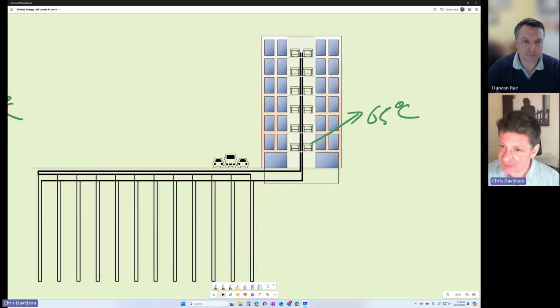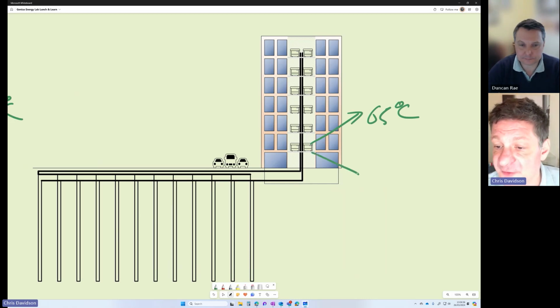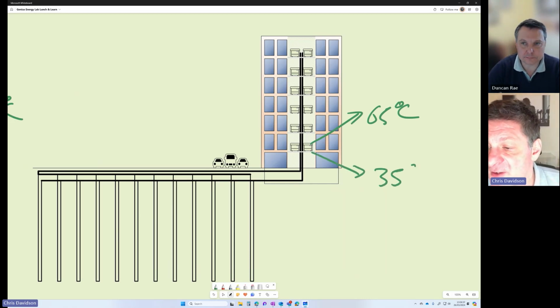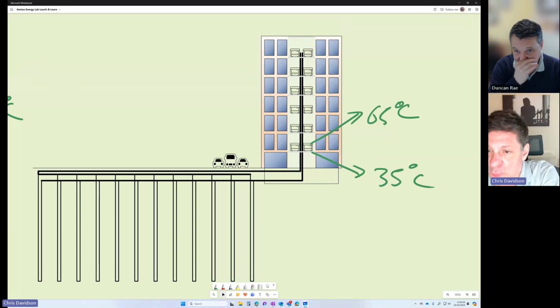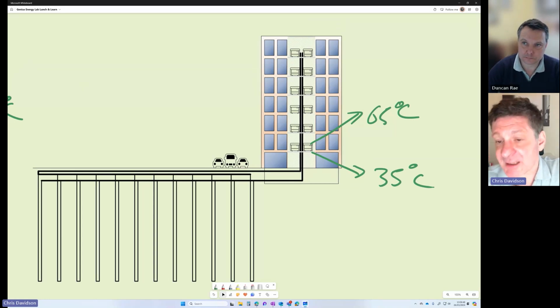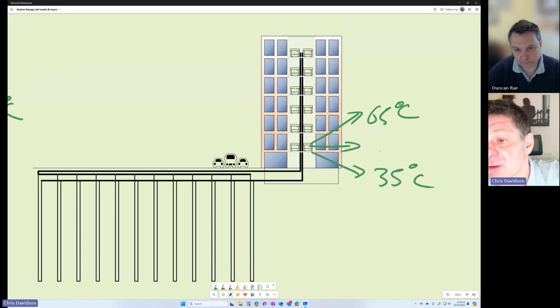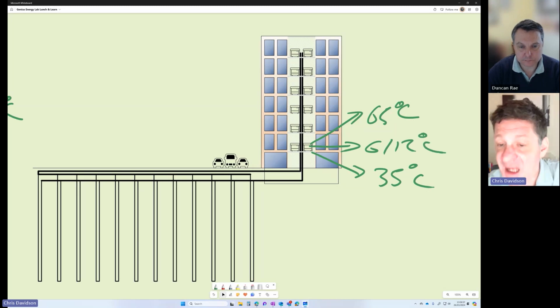And then they can turn off at that higher temperature and go to a lower temperature to deliver the space heating at 35 degrees. So we're now not compromising that space heating efficiency in order to deliver that domestic hot water. We could also be cleverer. Again, we could reverse that heat pump just as we did in the commercial building and deliver cooling, let's say 6 to 12, which would be typical cooling temperatures. Or we could even use that ground loop directly to do that cooling as well.